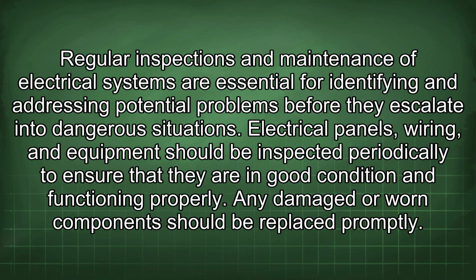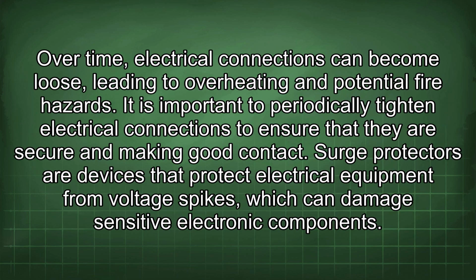Regular inspections and maintenance of electrical systems are essential for identifying and addressing potential problems before they escalate into dangerous situations. Electrical panels, wiring, and equipment should be inspected periodically to ensure that they are in good condition and functioning properly. Any damaged or worn component should be replaced promptly. Over time, electrical connections can become loose, leading to overheating and potential fire hazards. It is important to periodically tighten electrical connections to ensure that they are secure and making good contact.